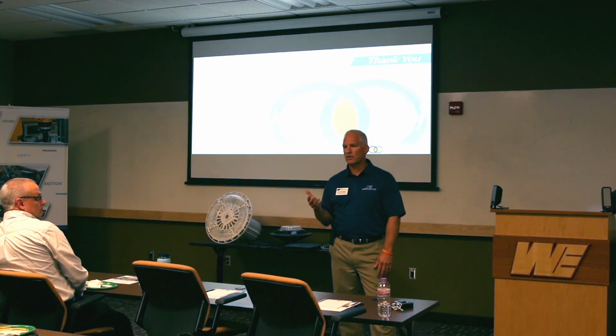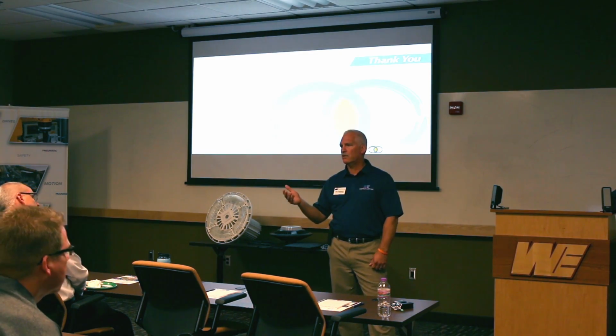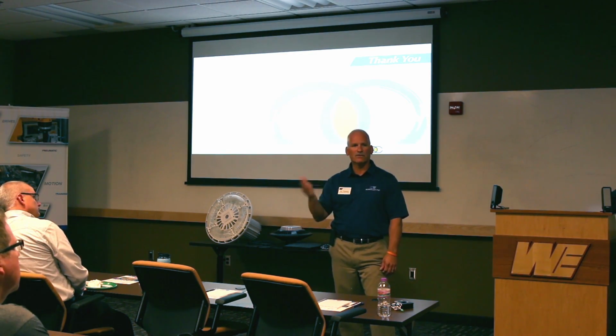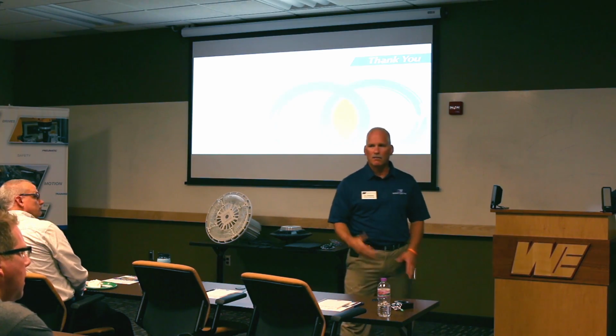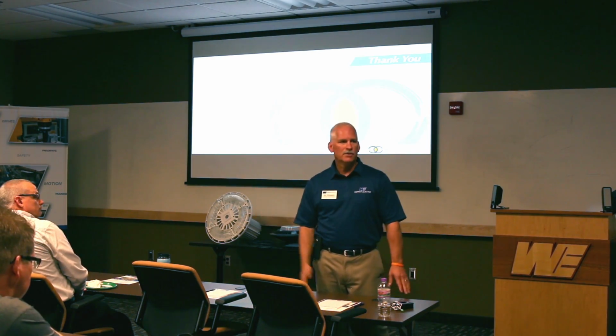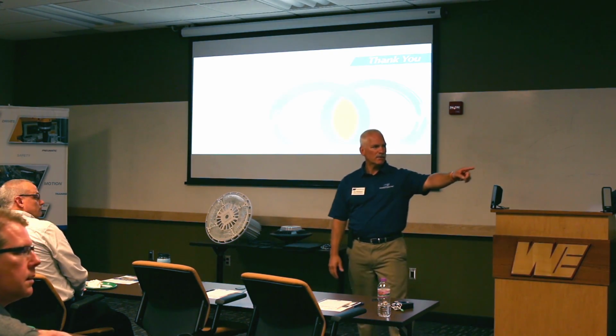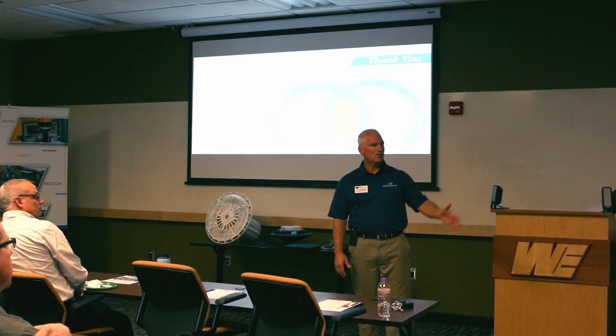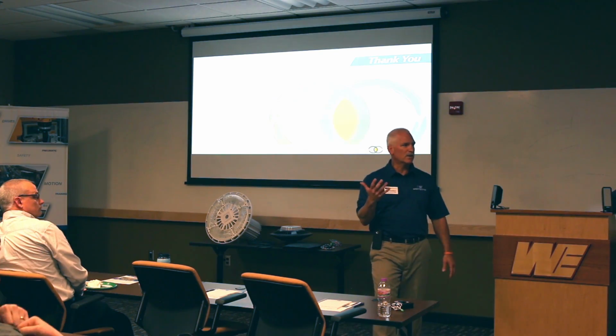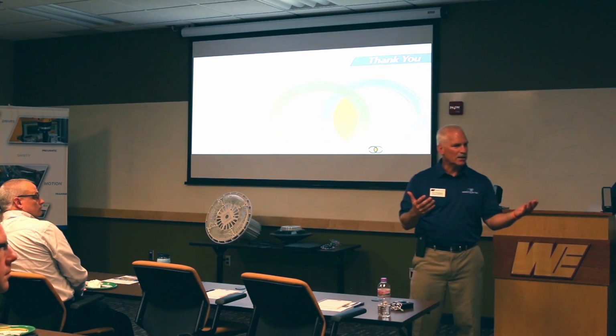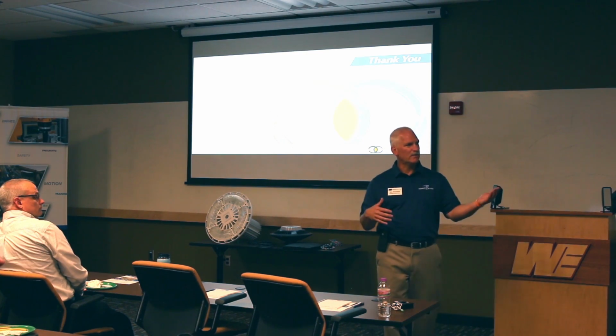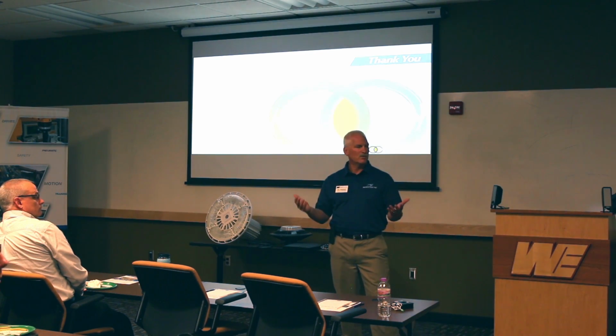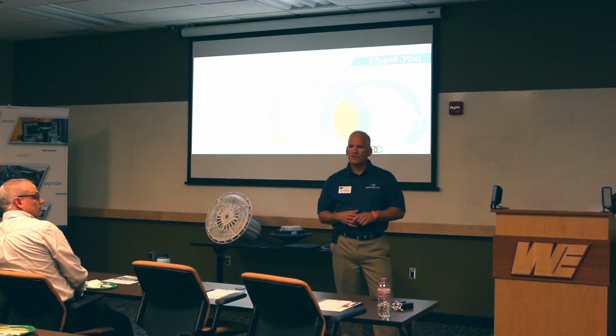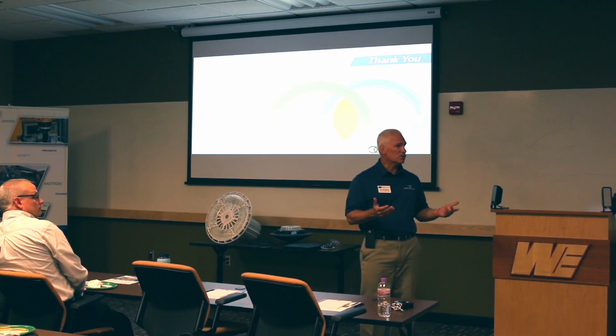Harmonics are multiples of a base frequency. So if it's a 60 cycle system, a harmonic is a multiple of that. You mentioned fifth or seventh - if you have 6 devices converting power, you always get the harmonic that's one less and one more than that. So you have a lot of fifth and seventh if you have variable frequency drives because there are 6 pulse devices. So the question is, what's too much?